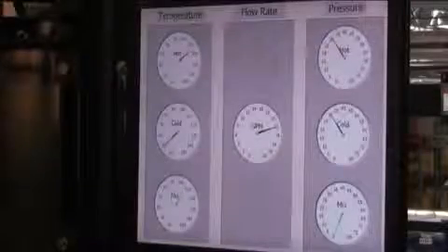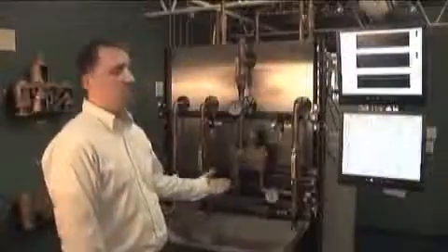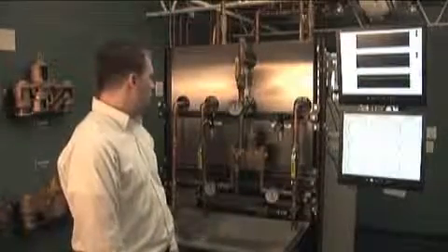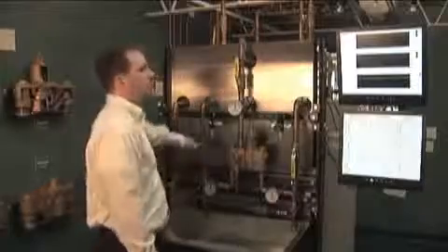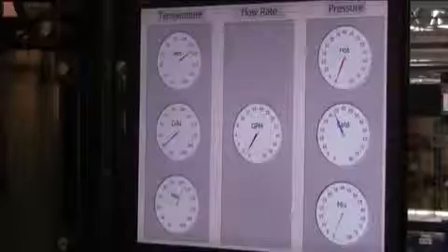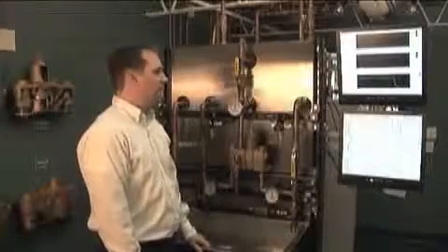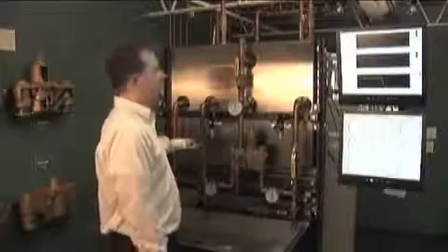Now what about the catastrophic events that might occur? What happens if the valve were to lose hot or cold water at any time? If the valve loses the hot water, the thermostat responds by shutting off the flow from the mixing valve, almost down to nothing, within a half a gallon or less. Once I reintroduce the hot water into the valve, within a matter of seconds, I will come back to the desired set point.